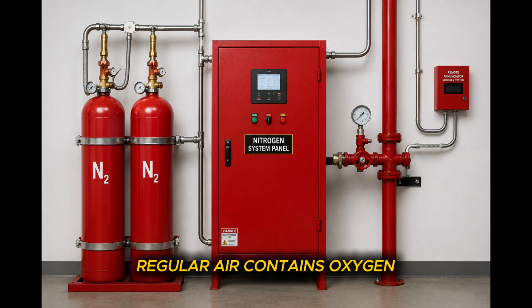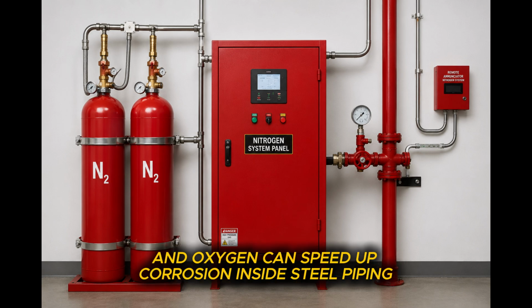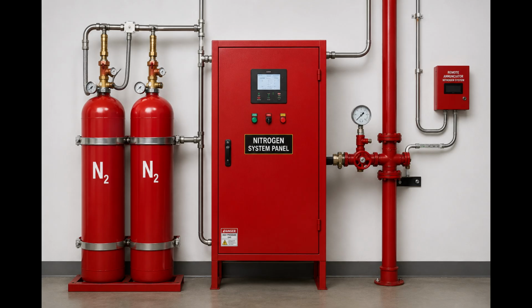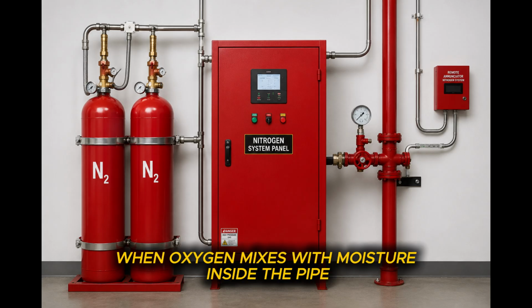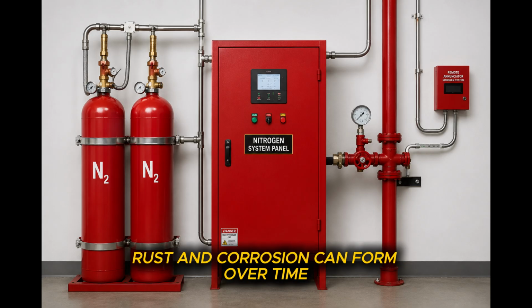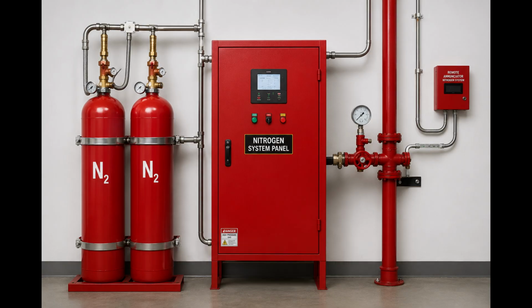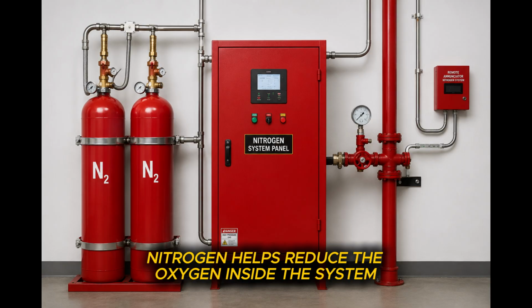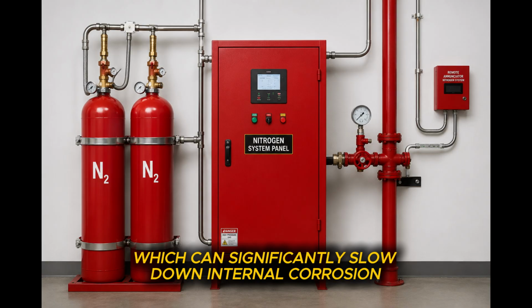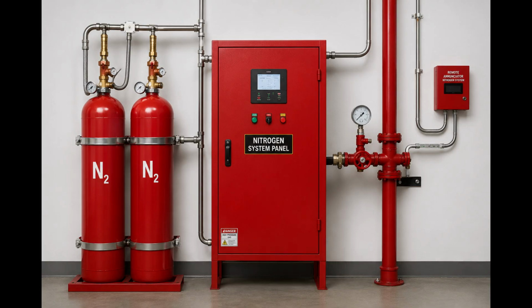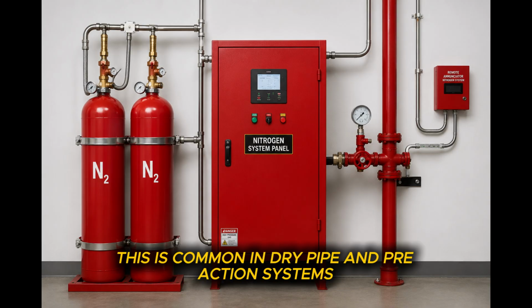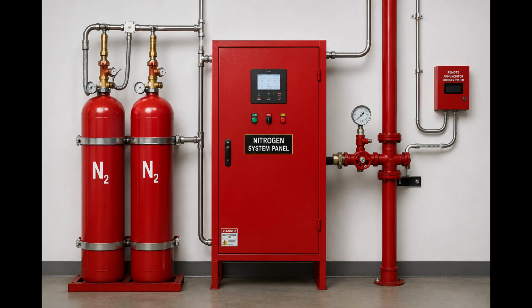Regular air contains oxygen, and oxygen can speed up corrosion inside steel piping. When oxygen mixes with moisture inside the pipe, rust and corrosion can form over time. Nitrogen helps reduce the oxygen inside the system, which can significantly slow down internal corrosion. This is common in dry pipe and pre-action systems.